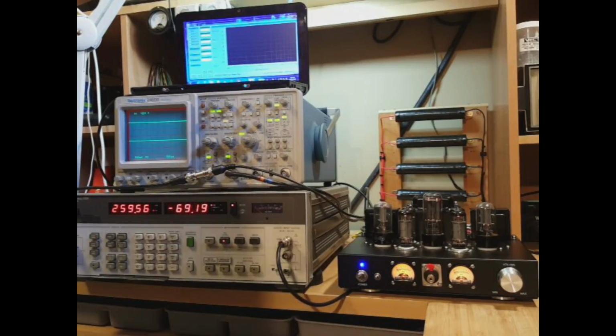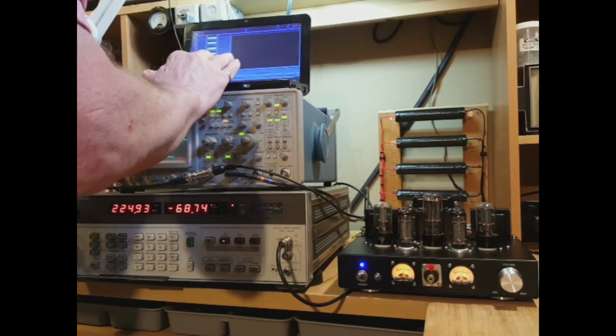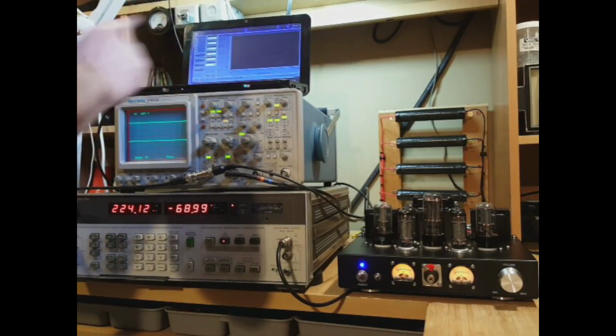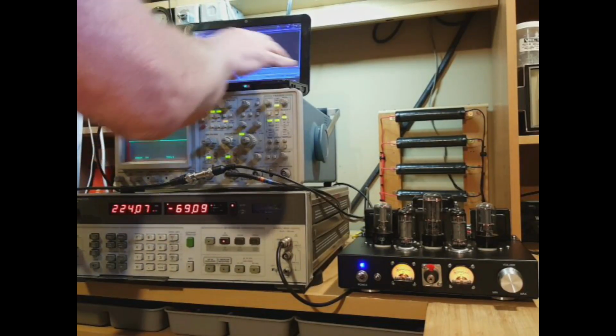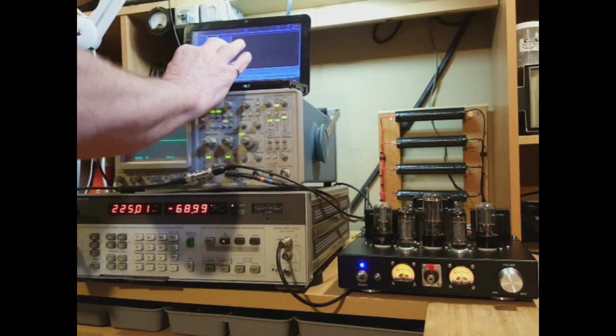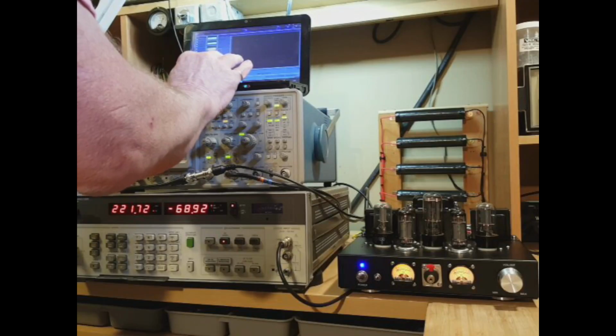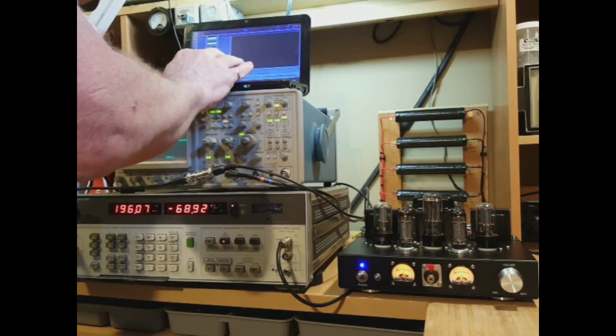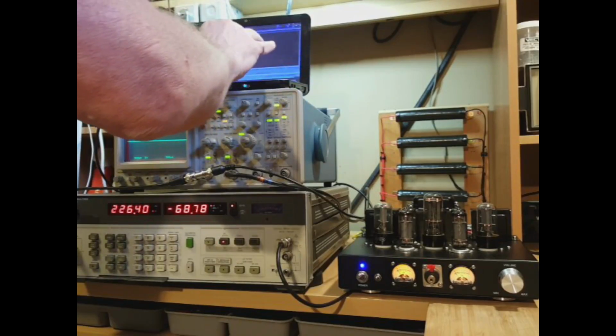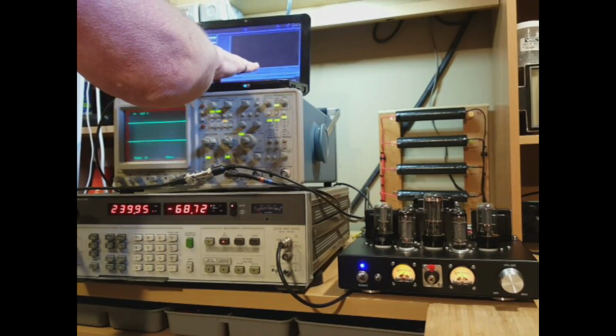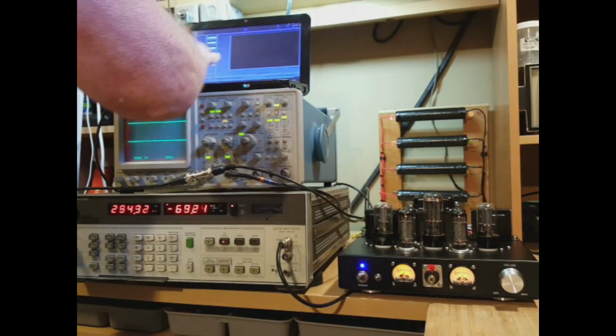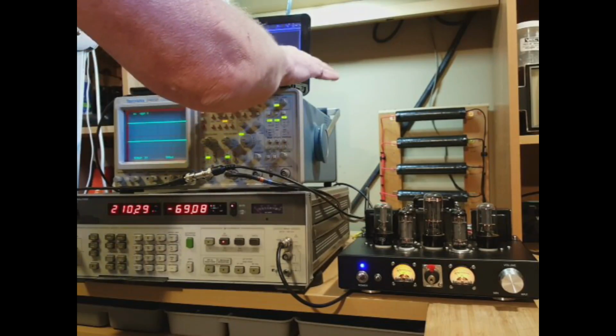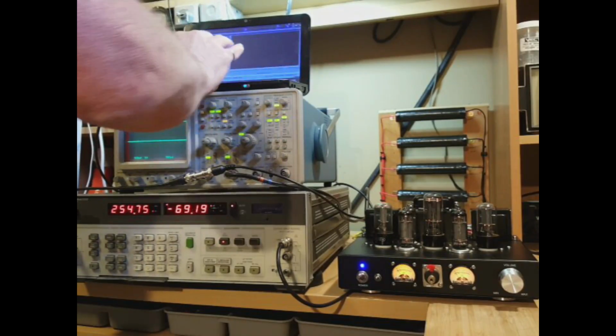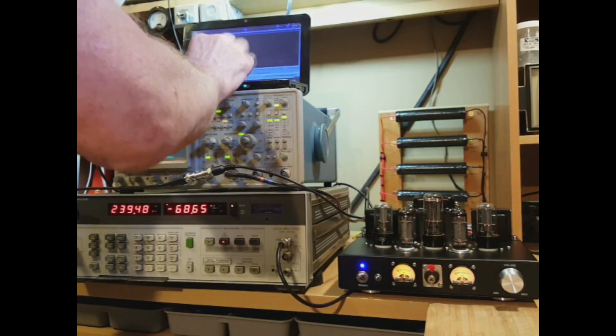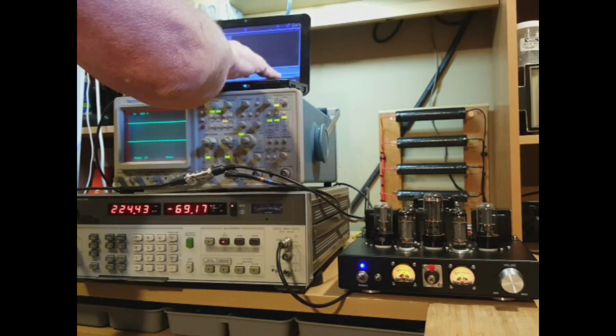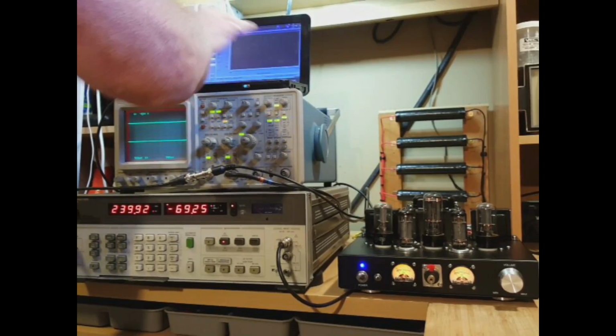So if you would permit me, I'm going to set this up. We'll go to 5%. We're going to use the same test frequency of a kilohertz. We're going to put in 10 points per decade. And level, excuse me, that is a voltage. So we're going to go to 1 volt, and we'll see what goes on with it. Let's go nuts, 1.5 volts, because that's the most you're probably going to get out of a preamp device. Our maximum total harmonic distortion, we'll call 7%.